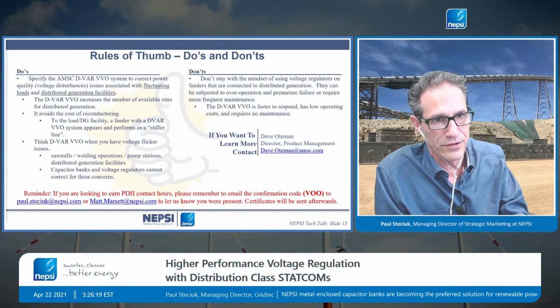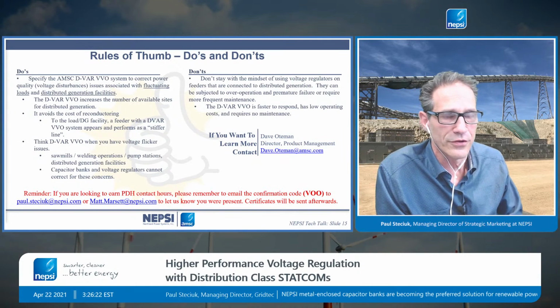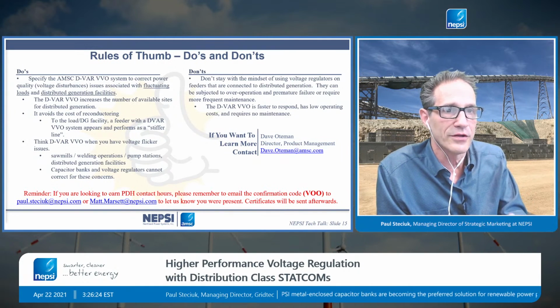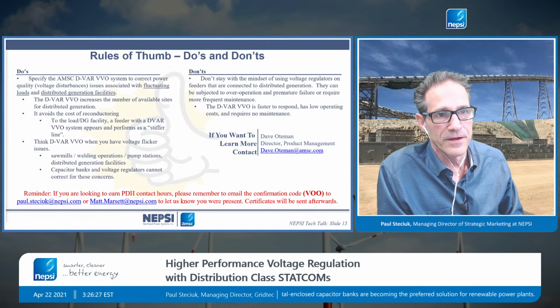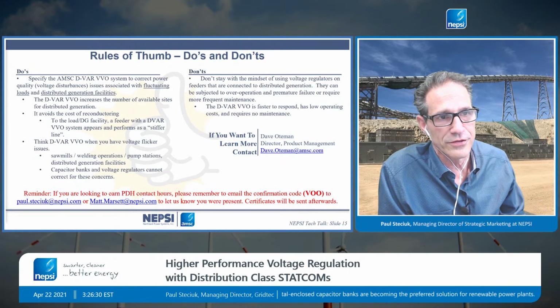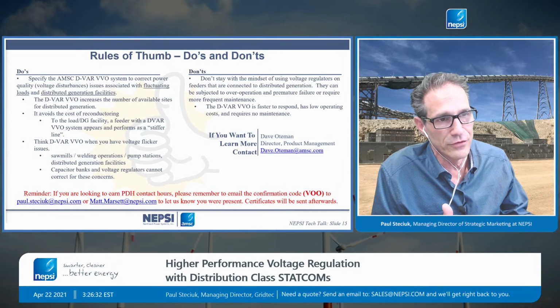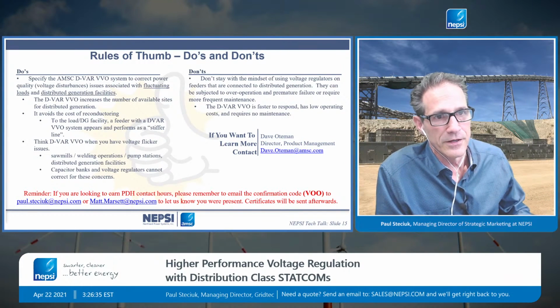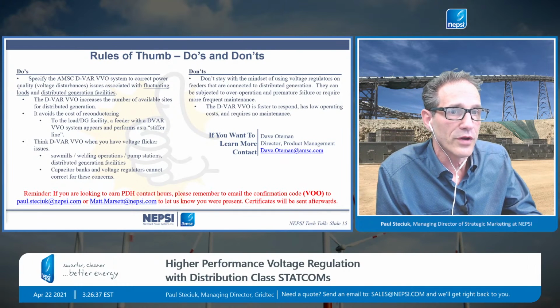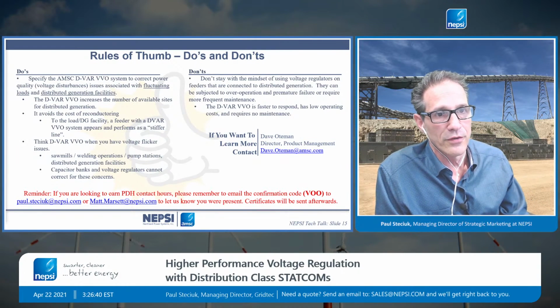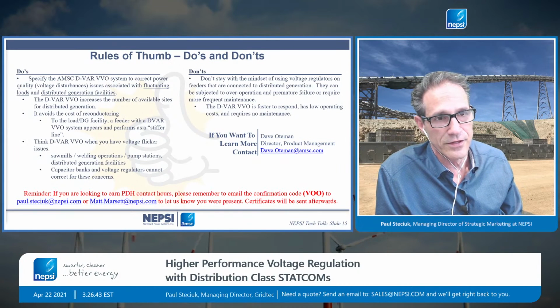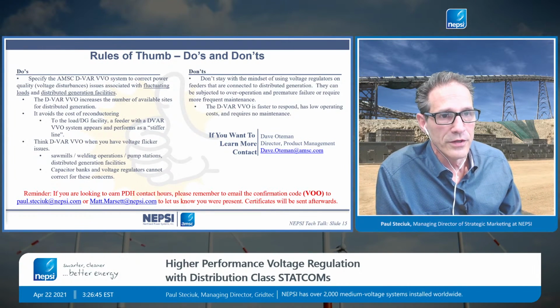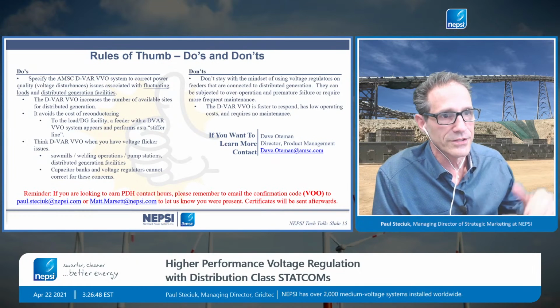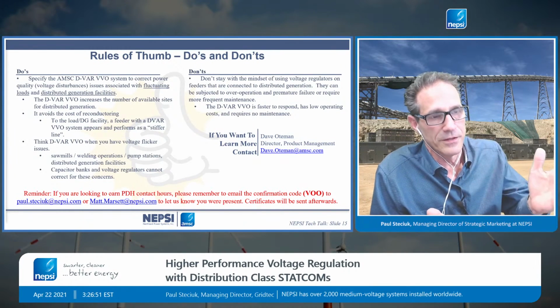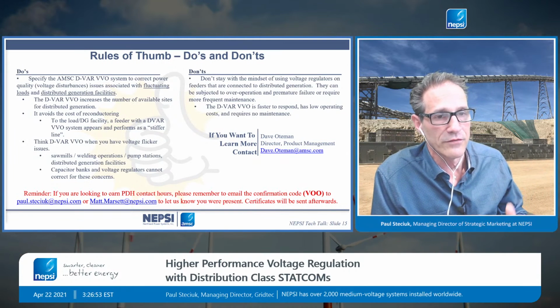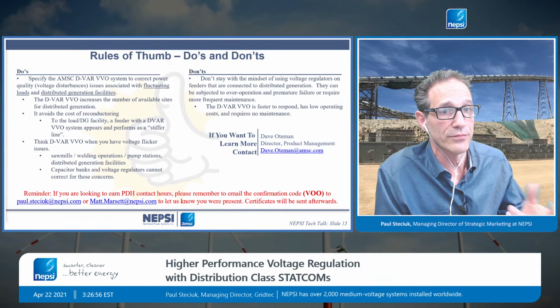Now for the don'ts. Don't stay with the mindset of using voltage regulators on feeders connected to distributed generation sites. If your mindset is 'I need to correct voltage, so I'll use a voltage regulator,' understand that voltage regulators can be subjected to over-operation, premature failure, or require more frequent maintenance. This is especially true with solar as a distributed generation site, since each time a cloud passes over, the voltage regulator tries to maintain voltage, causing a switching operation and premature failure.